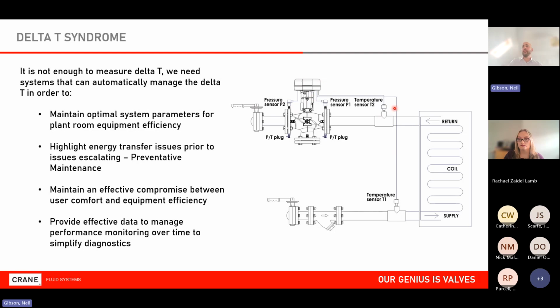So a traditional way I would have done that is I would have separate temperature sensors. They would report the information back via the BMS. A logic is created in the BMS to use that information to drive a command to the valve to compensate. No one does that because it's overcomplicated. So we just leave it to drive 0 to 10 volts, thinking it's doing what it should be doing.